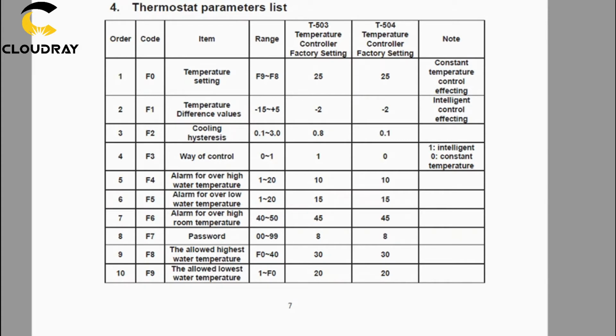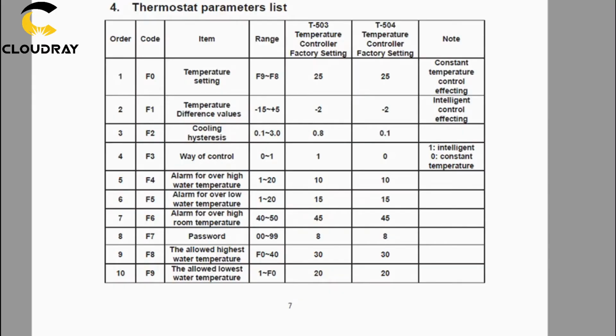The constant temperature mode is basically that. I can set the water temperature at what I want it to be maintained at, and then it will just maintain that between a plus and a minus from that set temperature. But if you have a look at F0, the temperature setting range, and F8 to F9, it's got code F0, temperature setting, range F8 or F9 to F8. If you look at the bottom of this chart, you'll see F8 and F9 are the highest and lowest allowed water temperatures. Their defaults are 20 degrees at the lowest and 30 degrees at the highest. So what this means is that if I want to change F0, I can't go below 20 degrees and I can't go higher than 30 degrees.